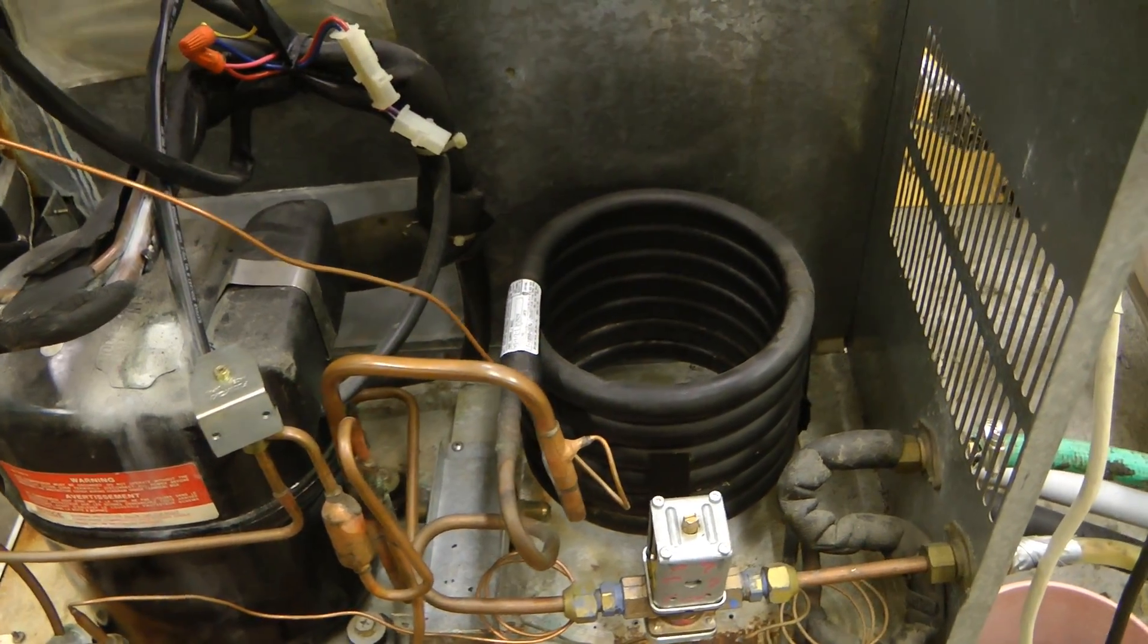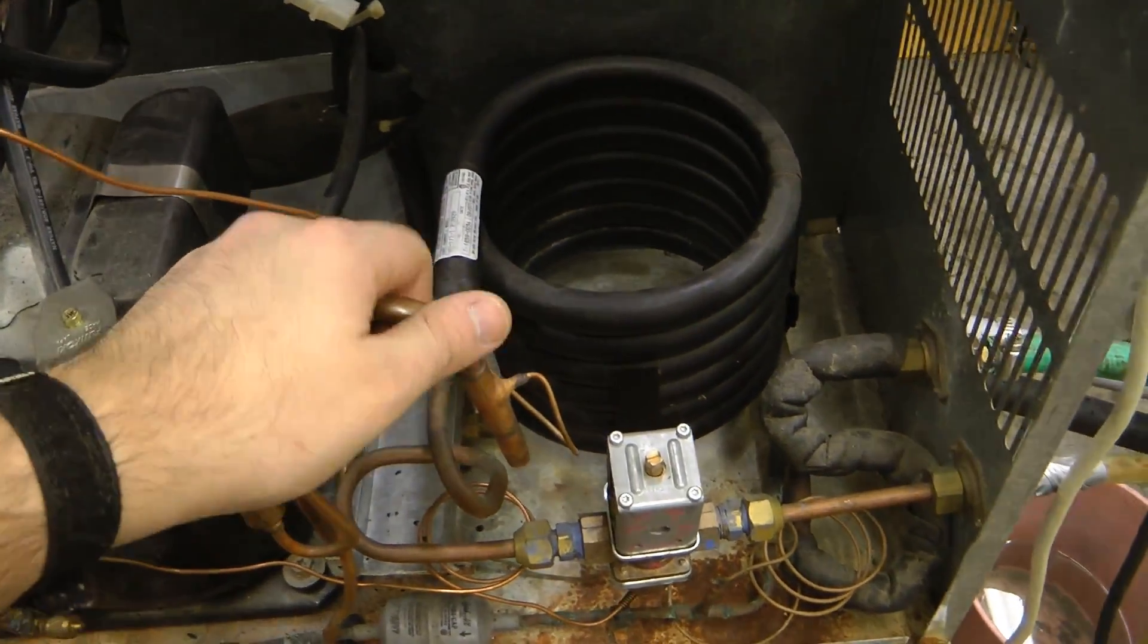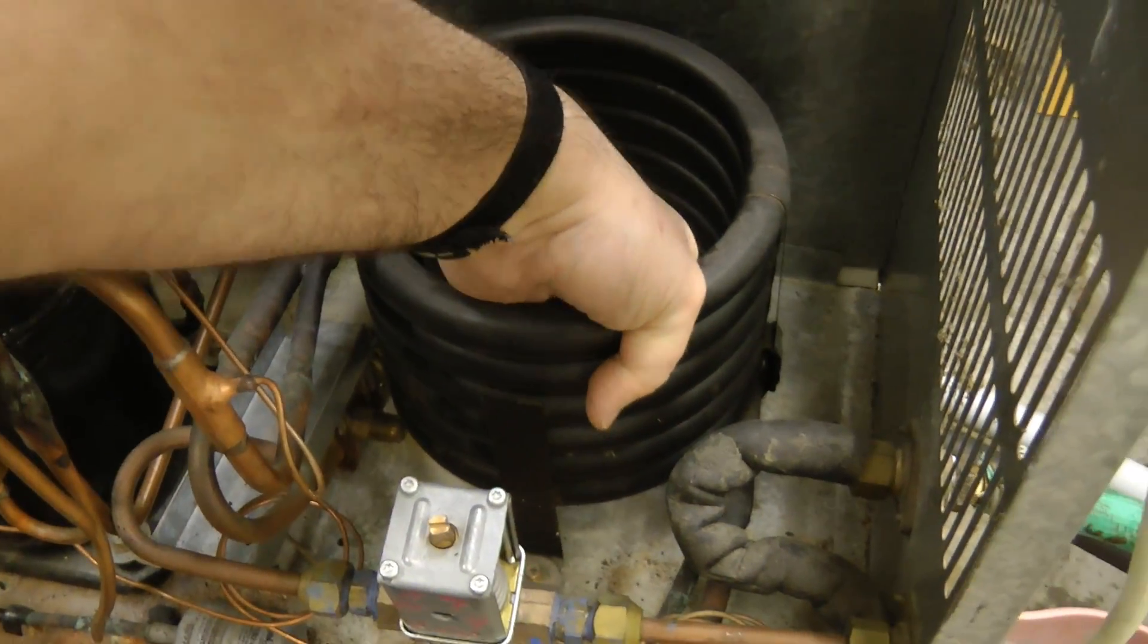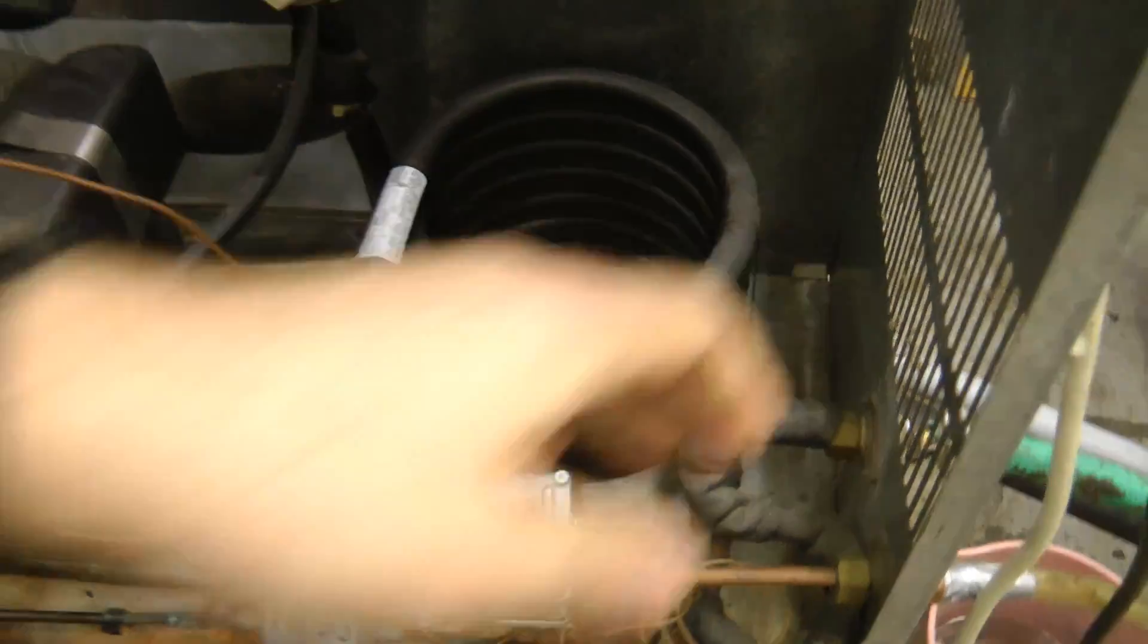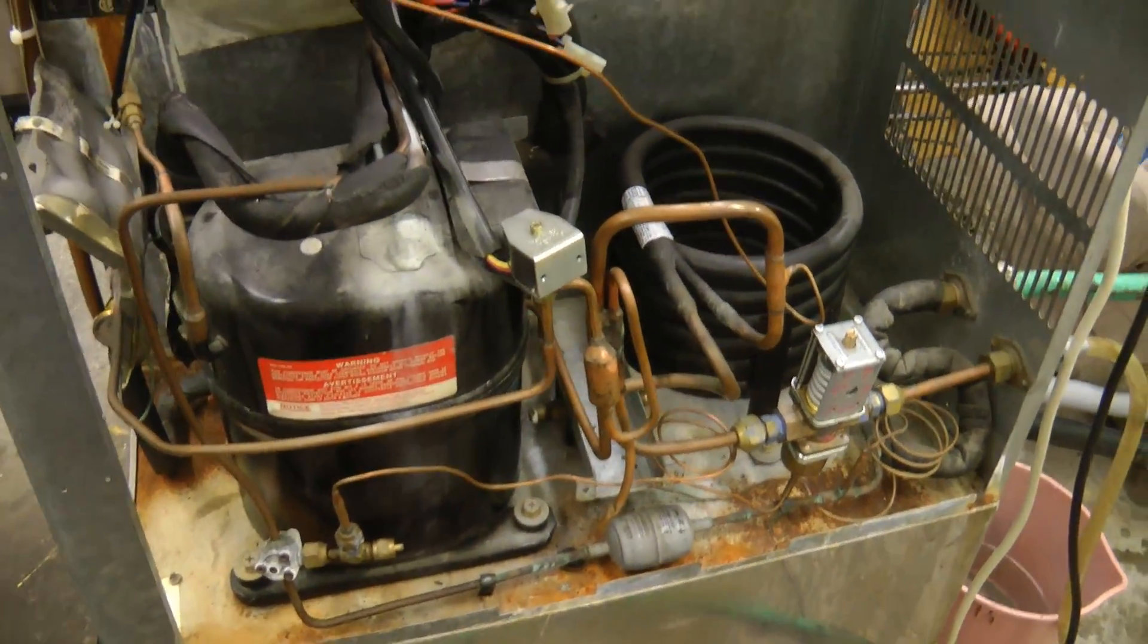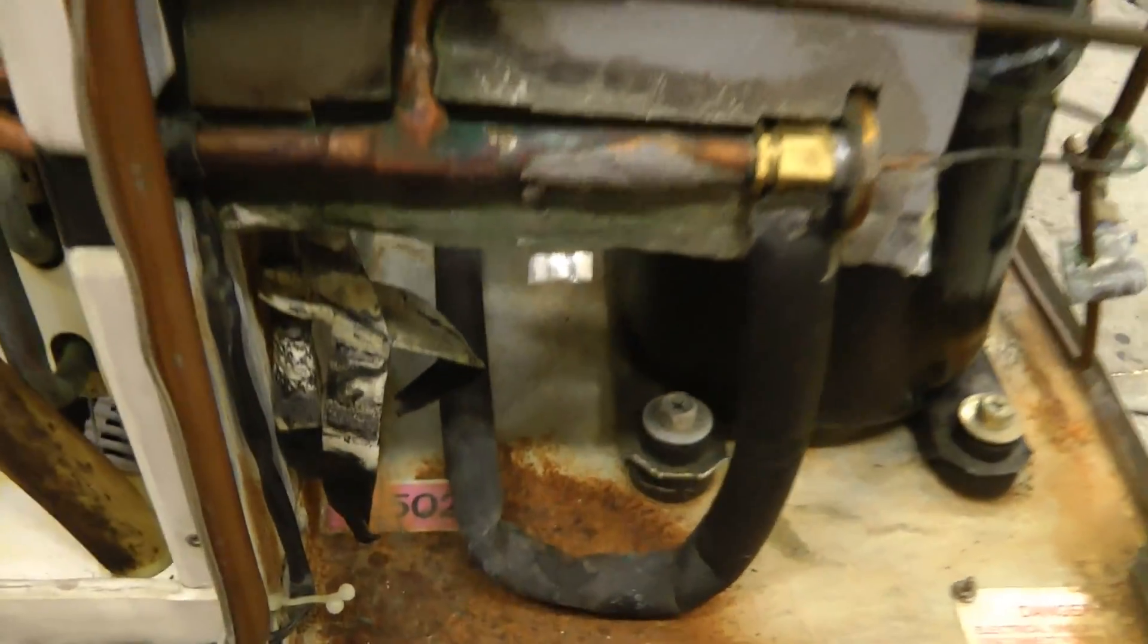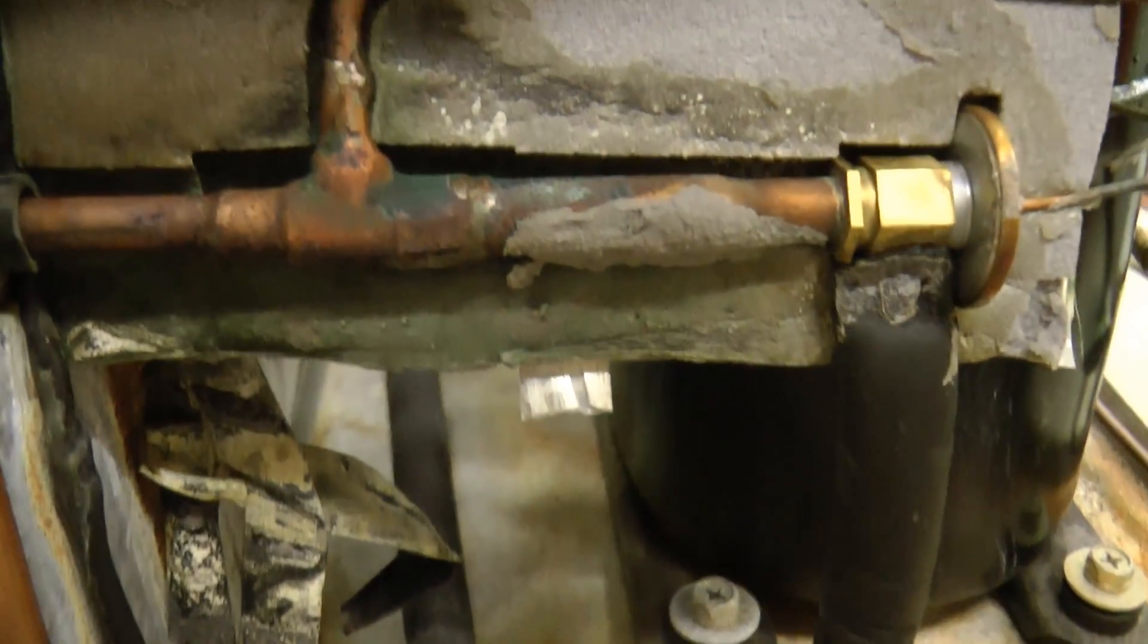This has been running for over fifteen minutes now and this is still not really that warm. Like I can still hold my hands on that and this is essentially cold. So I have to conclude that they did recover the refrigerant or just almost all of the refrigerant has leaked out. You can definitely hear hissing around this valve as well.